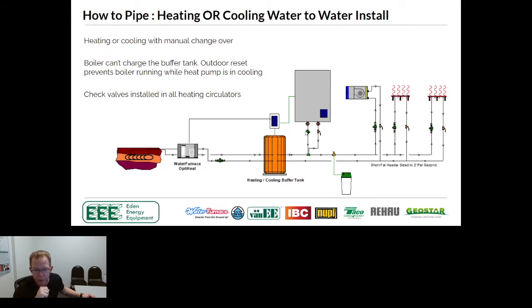The concept here is that if we've got 120 degree water in the buffer tank, this boiler is only lifting it 20 degrees. We're using this boiler to monitor the buffer tank, and that's what tells the boiler to come on. So the boiler only comes on when there is a heating call, which is a catch. Again, you've got to know what you're doing. Be prepared. Make sure it only comes on with a heating call, not a cooling call. And it'll come on with a heating call when the tank is not hot enough to produce usable heat.